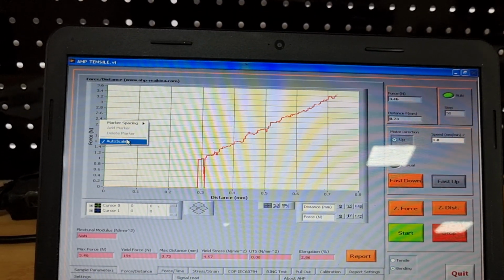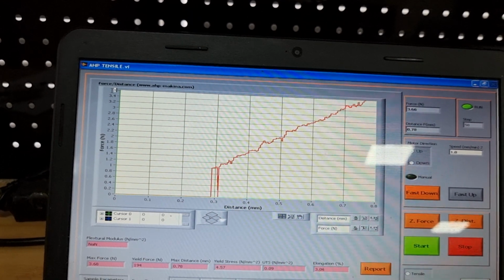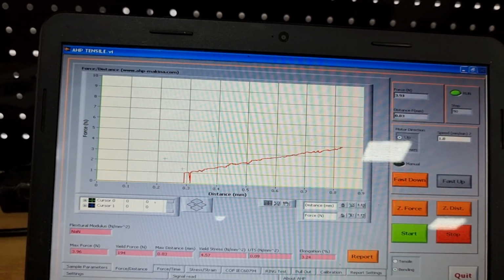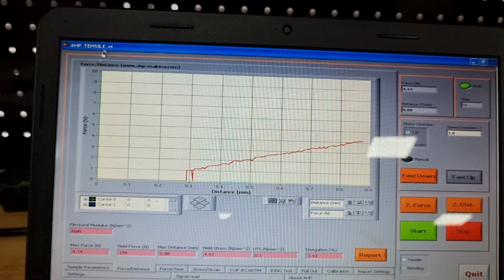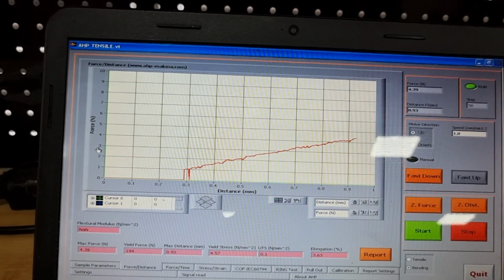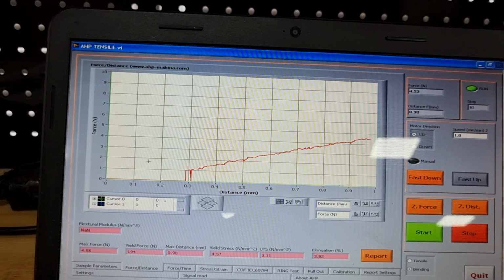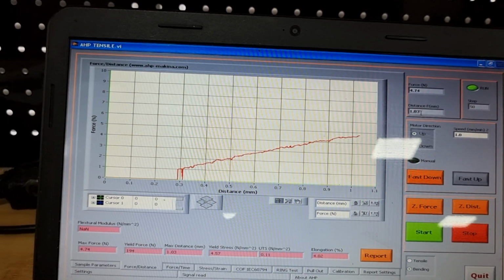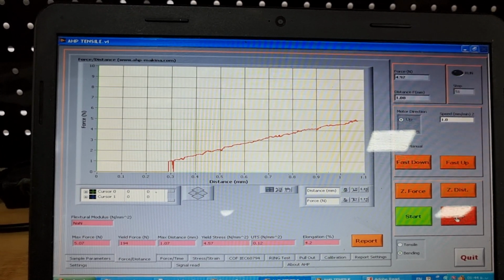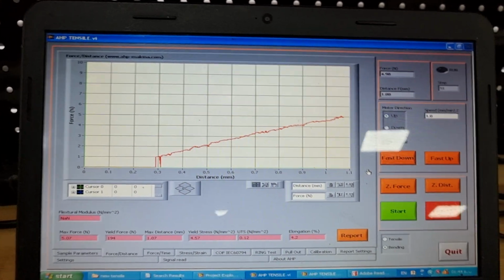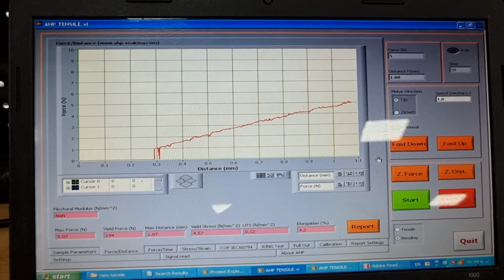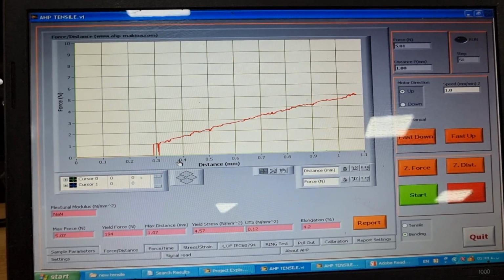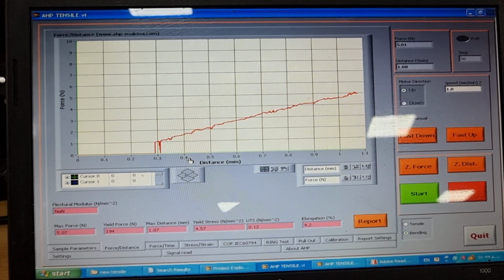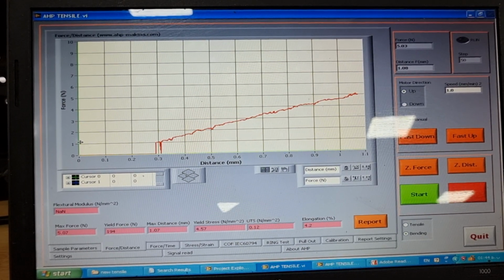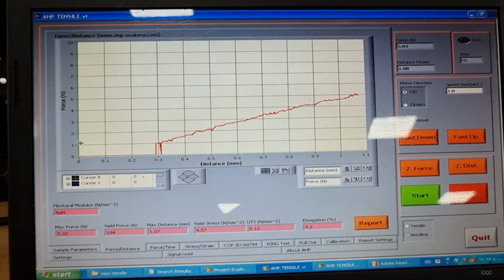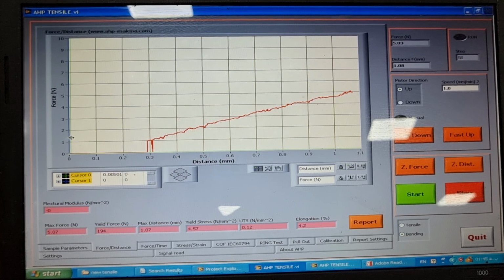Now the graph is very zoomed. Here you can also define the top and bottom levels for the scales. Vertical scale is the force, and the horizontal is distance. 1 millimeter displacement is enough for the measurement of flexure. I'm just clicking on stop. Because the flexure is measured at very low displacement values. For example, the first displacement is about 0.1 millimeter, and the second measurement point is about 0.564, and it depends on the thickness and dimensions of the samples.